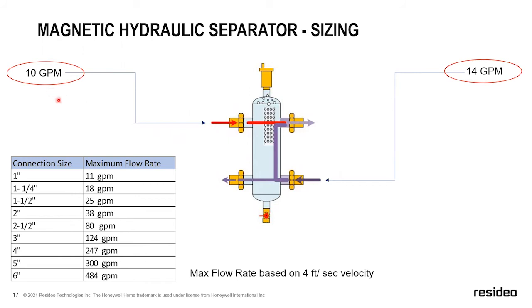So here's my 10 gallon a minute example again. Let's say we've got our boiler sitting over here and it's been designed with 1 inch piping. You're kind of maxing out 1 inch at 10 GPM, but I'm just going to use that as an example. So the boiler loop is 1 inch. Out here on the system side, we'll go back to that zone pump example. Well, if we've got the capacity to drive 14 gallons a minute, we really need to be on 1.25 inch piping now. So if you look at this, what size hydraulic separator do you use?